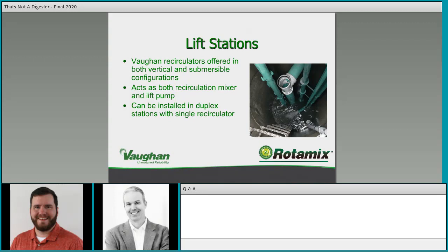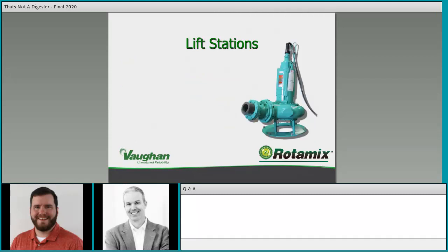The recirculation pump runs constantly and the other pump constantly discharges during high flow periods, then cycles between recirculation and pump-out during low flow stages — with built-in redundancy that's necessary for many stations. We typically design for six turnovers per hour, which is a good working middle ground of not over-designing the flow while still being robust enough to handle anything thrown at it.